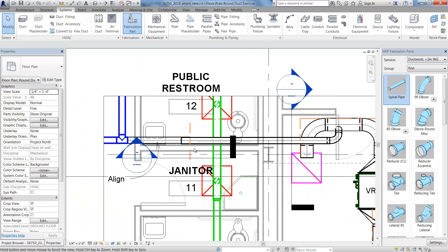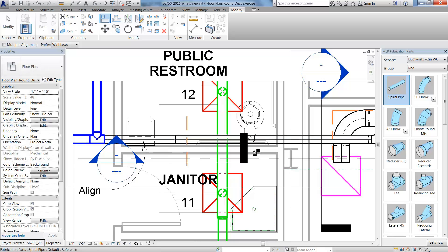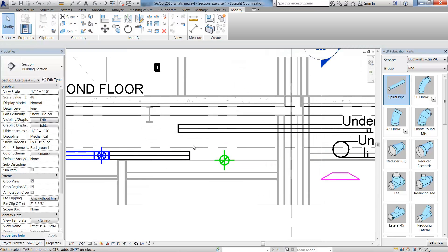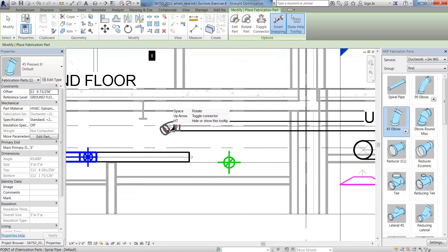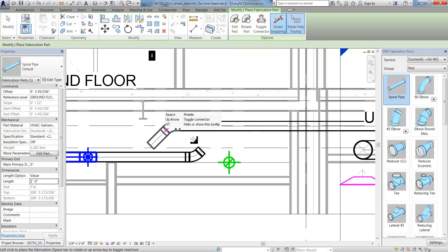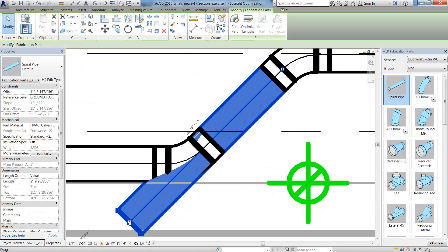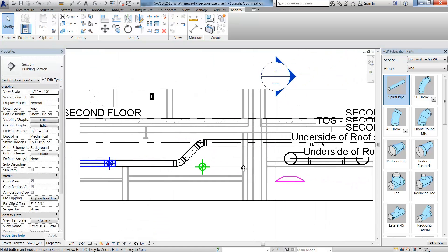When connecting two ducts on different elevations, you can use the Align tool to make the connection easier. You can add fabrication detail in the section views as well. Here you can add a 45 degree elbow to each duct segment and then add a one foot straight duct segment to it before aligning them. This makes it easier to connect by using the grips to connect both duct segments into a single branch.